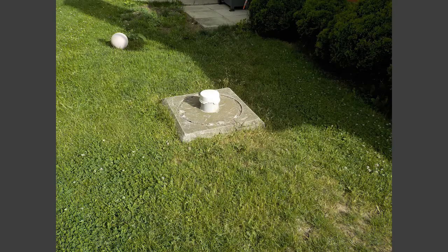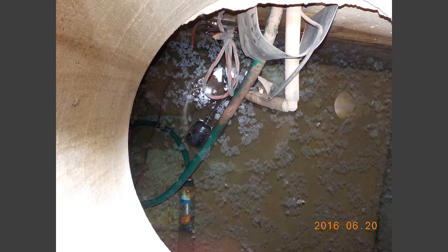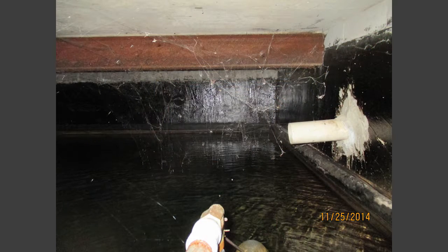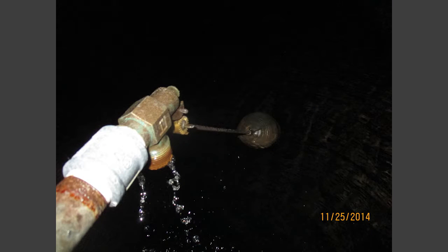What happens when homeowners on a rural property don't have access to a reliable water supply? The most common solution, if the owner has either a very low-yielding well or no water at all, is to put in a water storage tank called a cistern. These tanks can be either plastic or concrete and can be filled in a number of ways: from a low-yielding well supply, by collecting rainwater from downspouts and eavestroughs, or by having transported water delivered — or any combination of those.